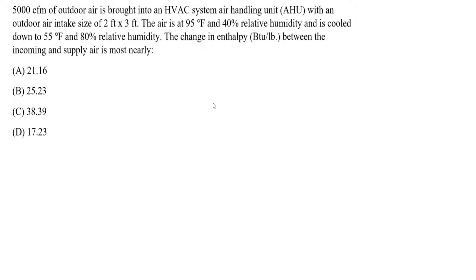So here we're looking at an HVAC system and we're specifically told we have 5,000 cubic feet per minute of outdoor air brought into an HVAC system with an air handling unit, an AHU, with an outdoor air intake size of 2 by 3 feet. The air is at 95 degrees Fahrenheit at 40% relative humidity. Then it is cooled down to 55 degrees Fahrenheit and 80% relative humidity. The change in enthalpy between the incoming and supplied air is most nearly what?